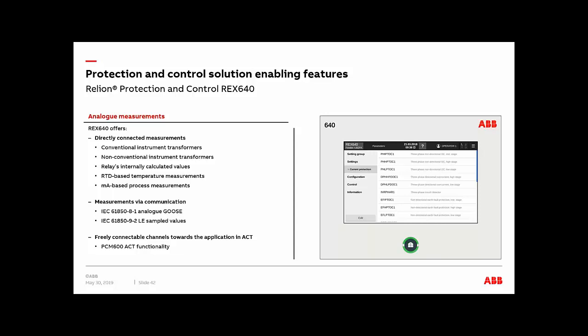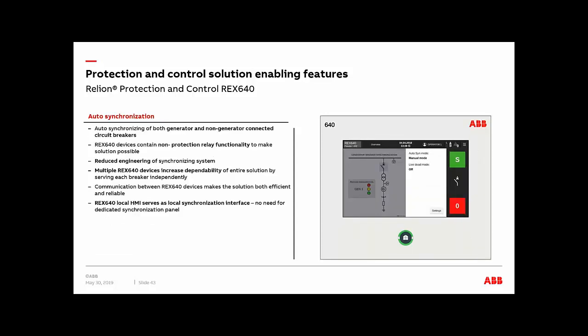640. When it comes to the auto-synchronization, auto-synchronizing both generator and non-generator connected circuit breakers, we saw a little bit of that on the package for auto-synchronizer. We have to remember 2 packages, one for generators and one for network breakers. So the REX640 contains non-protection relay functionality to make the solution possible. You can use it as a control box as well.